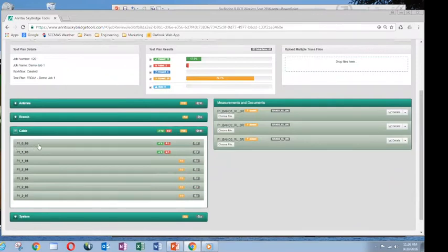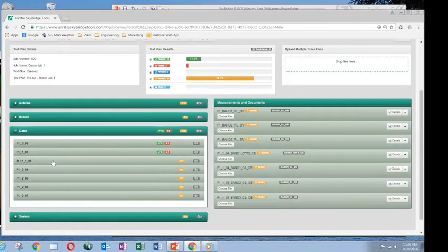And this naming scheme is an FBDA number, the next device, and how far the cable is from the FBDA. In this case, it's connected to the FBDA, it's at level 0. In this case, there's just 1 cable and 1 splitter between this current cable and the FBDA, and the next device is 03. So we call this a level and 2 ID naming scheme.